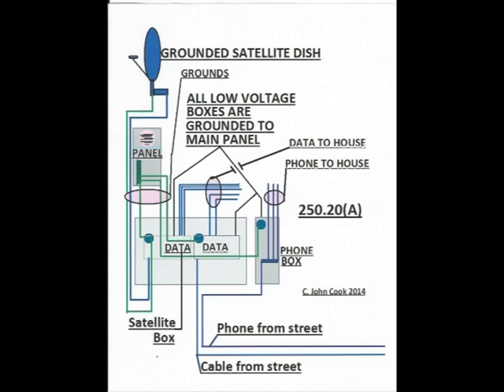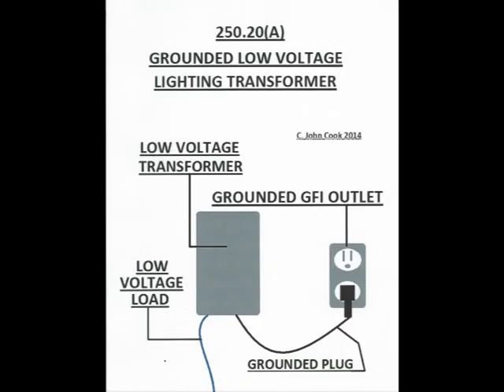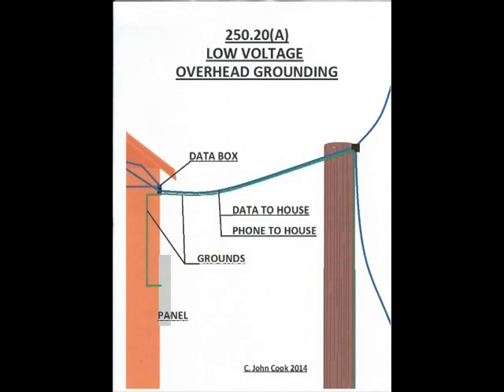In part A, you will not find a single word of what systems this code is talking about, so I will tell you. This article controls cable television — the cable splitter has to be grounded, as shown in the diagram. Telephone hubs, which is the box where the company links its phone wires to the building wires, as shown in the diagram. Satellite systems — the satellite dish has to be grounded all the way back to the cable hub, just like cable from the street or an overhead source. Malibu light transformers are also covered by this article, as well as all low voltage overhead wiring.